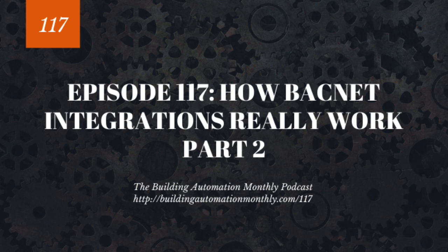Anywho, as I was saying, you've got these MAC addresses, and addresses 1 through 127 can be master and slave. Master devices allow you to initiate service requests and execute service requests, whereas slave devices can only execute service requests in response to a service request that's initiated by a master device. So slave devices are fairly useless. I know it's not something a lot of folks talk about, but it's just not very useful. If I had to choose to pay a little bit more to have a master device, I would, because it gives you more capabilities.